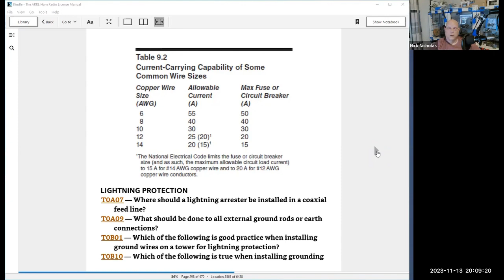National Electric Code sets the minimum at number 6 wire for ground wires. But if you're running 40, 50, 60, 80, or 100 feet, that's not a short connection. You're going to need some much bigger wire. The grounding book will tell you about that in detail. They won't ask you on the test. They'll just want you to know you should use bigger wire. I've already covered all this. Ground rods should all be tied together and all that.